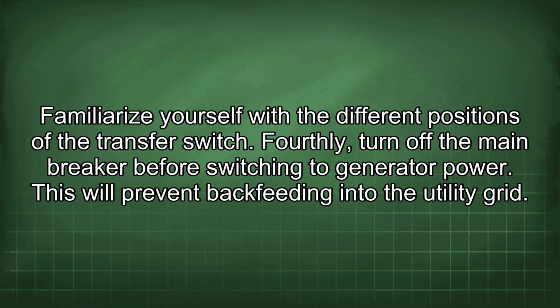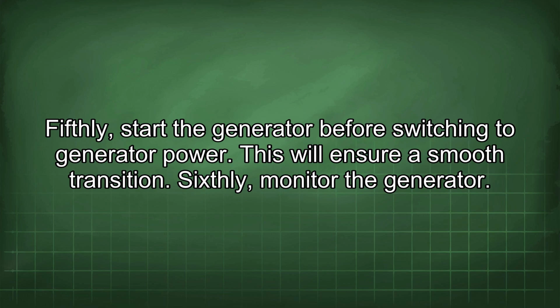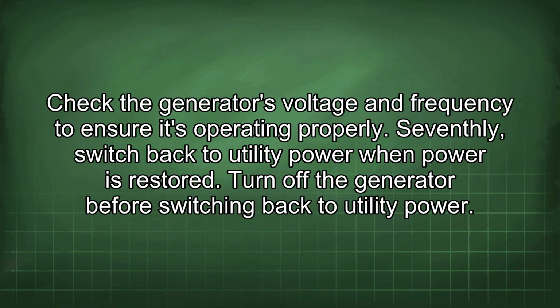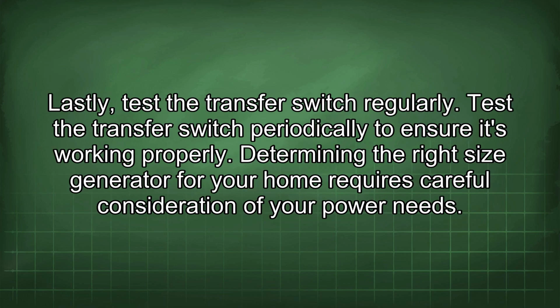Fourthly, turn off the main breaker before switching to generator power. This will prevent backfeeding into the utility grid. Fifthly, start the generator before switching to generator power. This will ensure a smooth transition. Sixthly, monitor the generator. Check the generator's voltage and frequency to ensure it's operating properly. Seventhly, switch back to utility power when power is restored. Turn off the generator before switching back to utility power. Lastly, test the transfer switch regularly. Test the transfer switch periodically to ensure it's working properly.